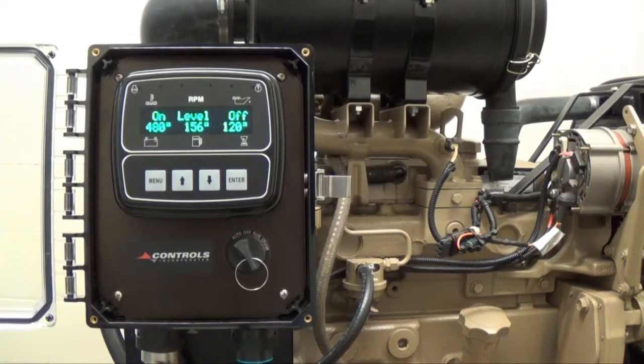When the Controls Incorporated module is placed in auto mode and no start command is present, the controller will automatically enter sleep mode after 2 minutes of inactivity. However, it should be noted that while the controller is in auto mode, any external input will cause the engine to start, such as floats or transducers.